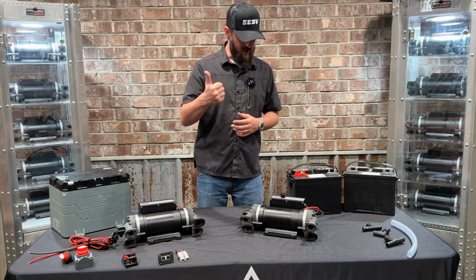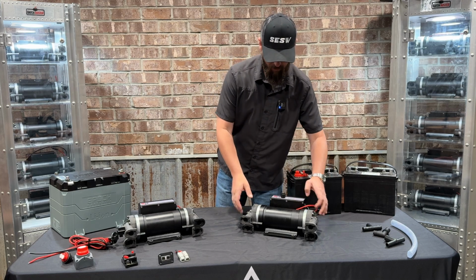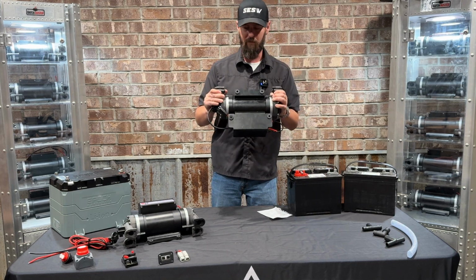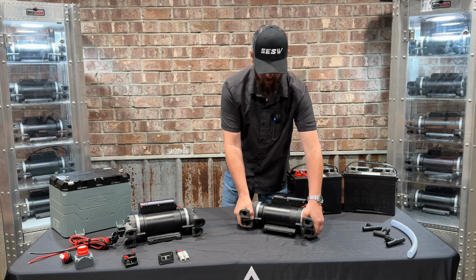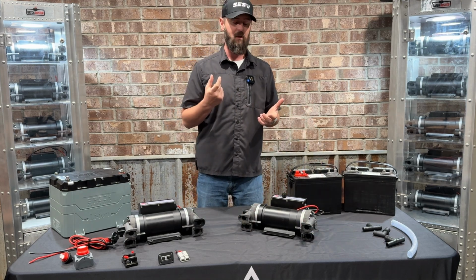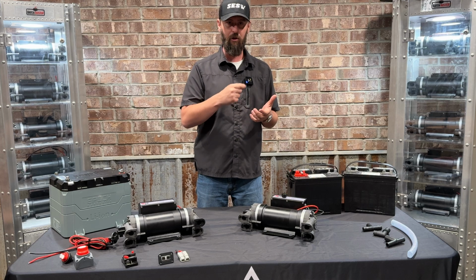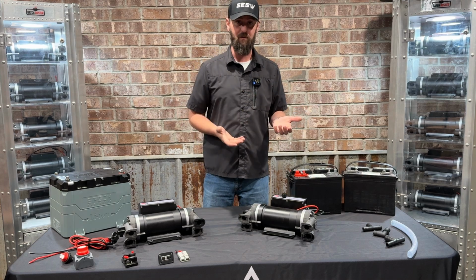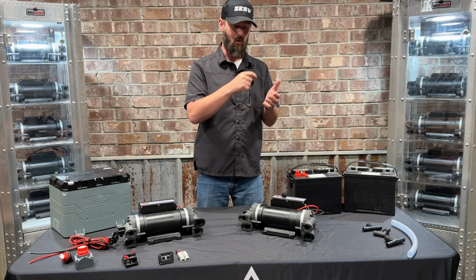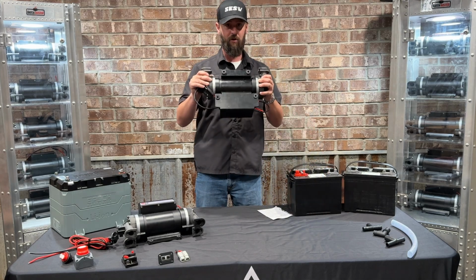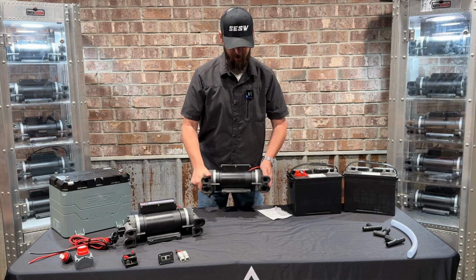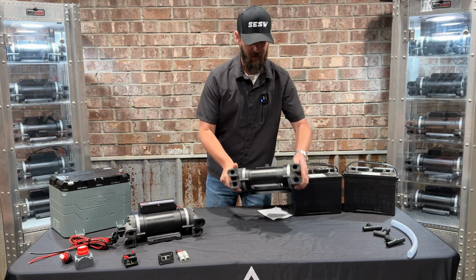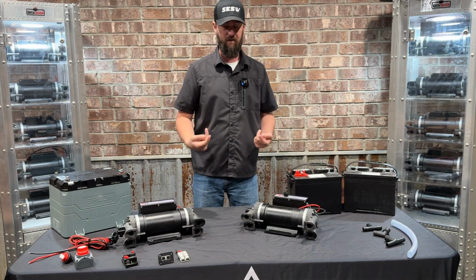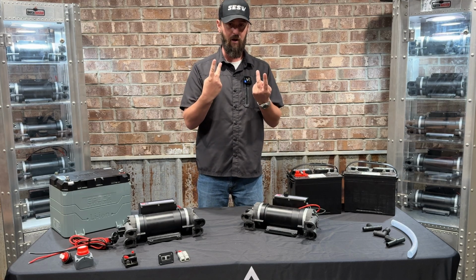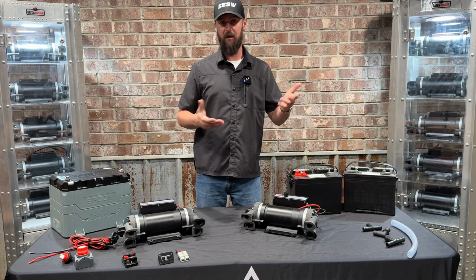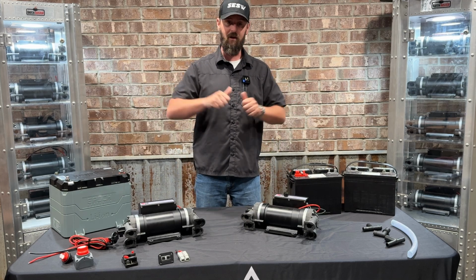So, quick attach footprint. Now, working off of that base, you guys see we've got some rubber mounting feet here on the bottom. The way we like to mount it, if you just got your pump out of the box, we like to take some True Blue or some pipe dope, something that's going to make a color, and we'll lay the pump on its back. We've done this for years with the other brands, and we'll mark us a little mark on the bottom of that rubber foot, all 4 of those, and then we're going to set it down where we think we want to mount it at and make 4 little marks, and then we'll take us a drill bit and drill those holes out and then run studs, permanent bolts, up through the bottom of wherever we're mounting it, trailer, skid, a shelf, whatever you're putting it on, and go ahead and run you a nut and lock those studs down.